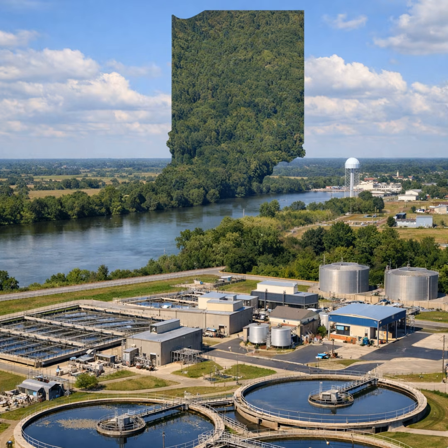And then the sludge age is greater than 10 days. Since it doesn't take in a lot, it holds it the longest in extended aeration. So they hold the sludge a very long time in the system. And the very last thing to note about an extended aeration process is that effluent suspended solids are usually higher, probably because the sludge age is so long. The suspended solids are usually higher because there's so much that's kept in the system.